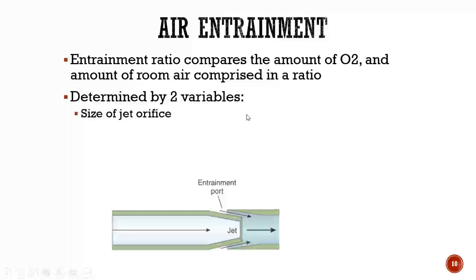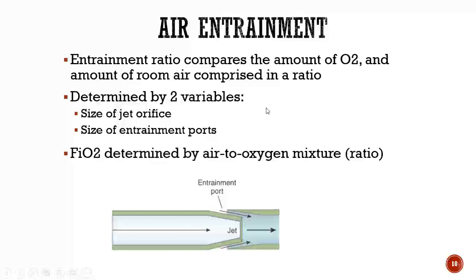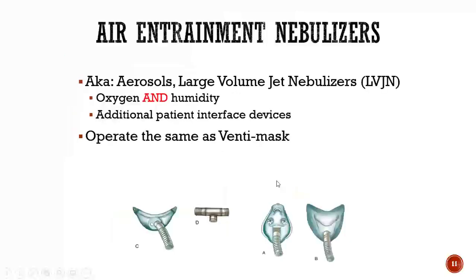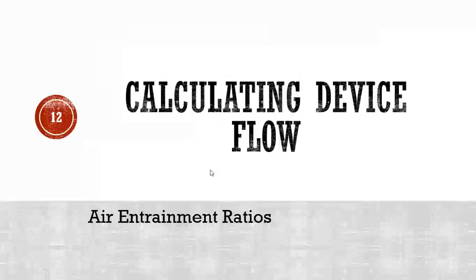For air entrainment, we look at two components: the size of the jet orifice and the size of the air entrainment ports. With these air entrainment masks or systems, the FiO2 is determined by an air-to-oxygen mixture ratio. The FiO2 does not necessarily change with the liter flow — you'll see examples of that more in lab.